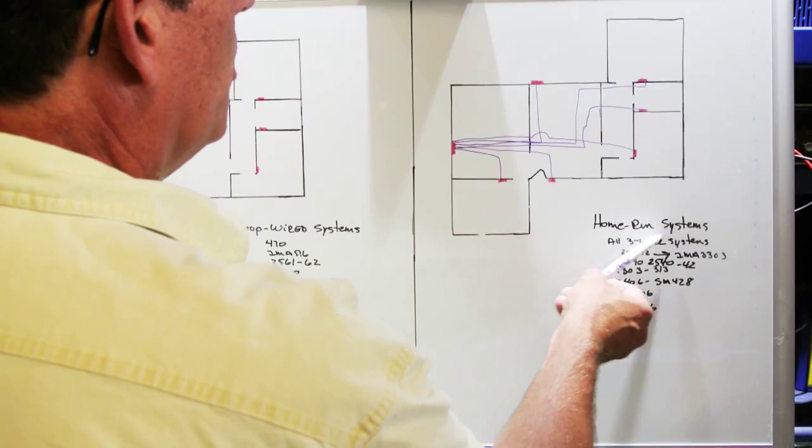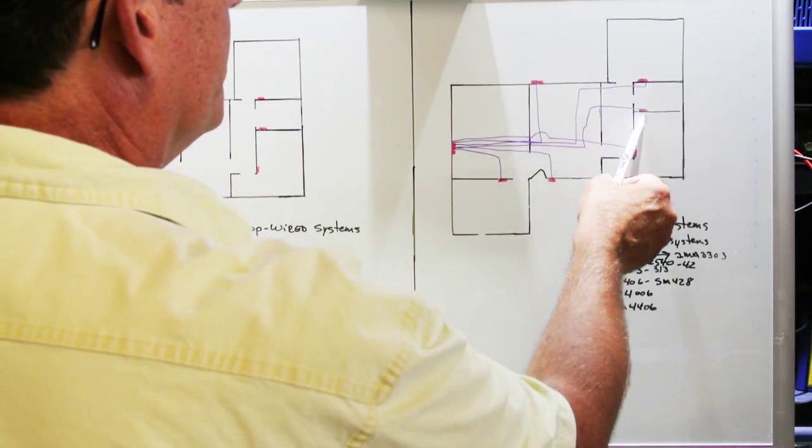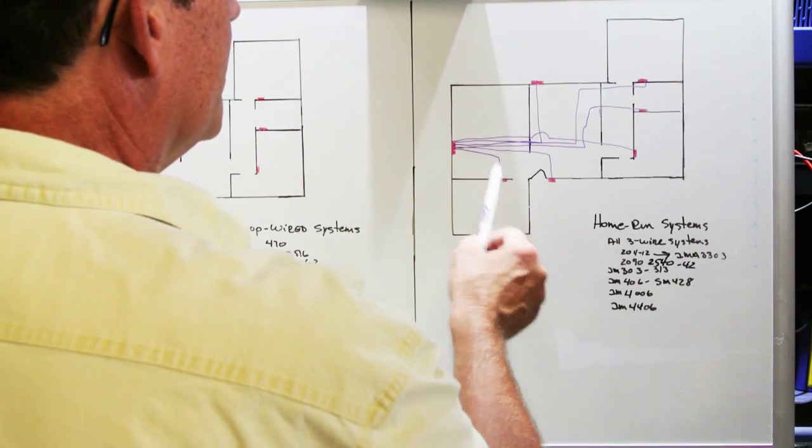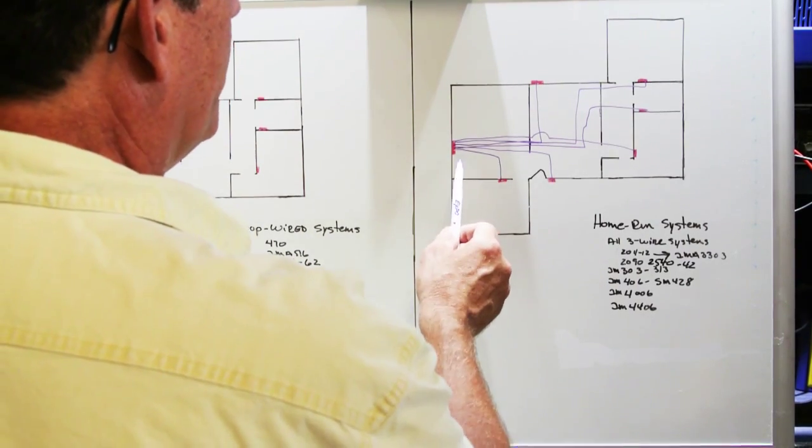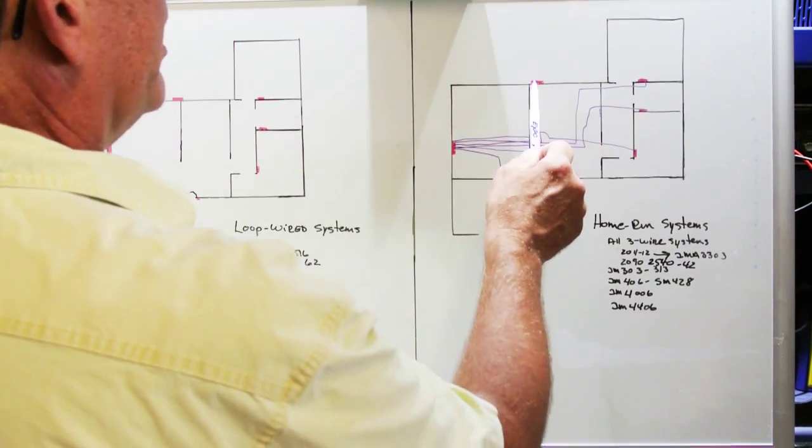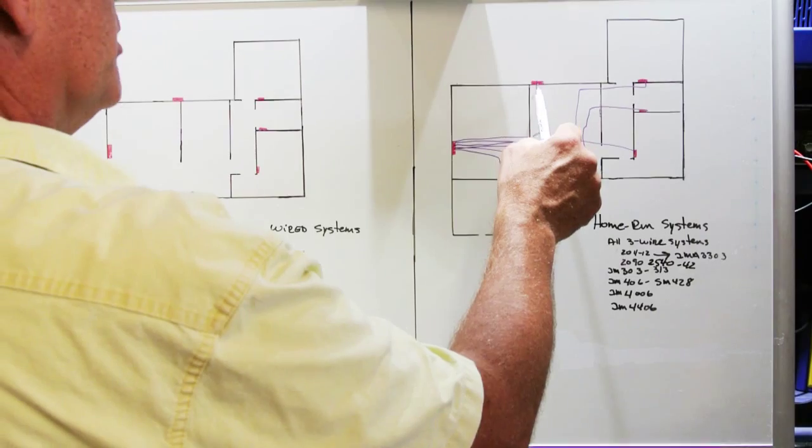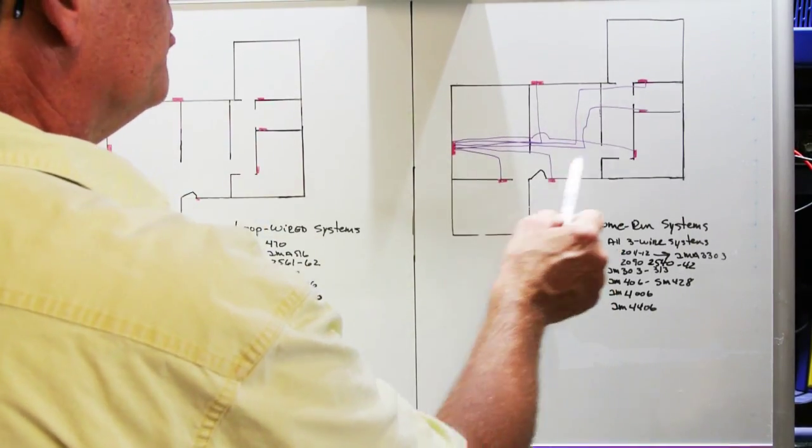What you'll see in home run systems is that if you have one, two, three, four, five, six remote stations, back at the master station, when you open it up, you're going to have six individual cables because the cable runs home from each station. So that's a home run system.